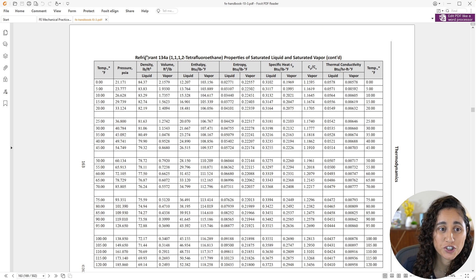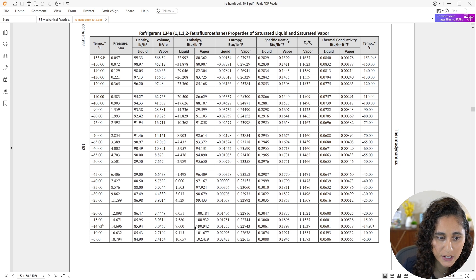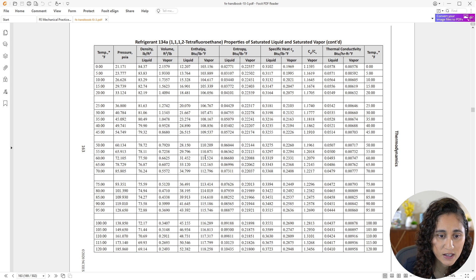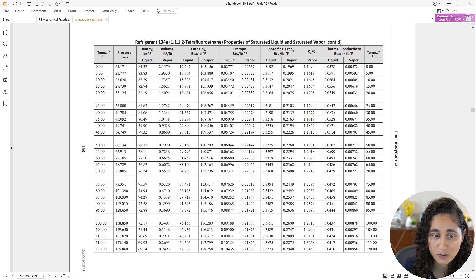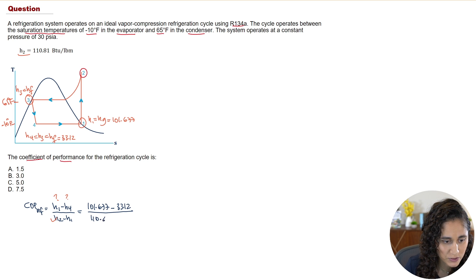Going to the reference manual for R-134A: at minus 10 degrees Fahrenheit, we look at the enthalpy columns for saturated vapor, and the value is 101.677. This is h1. Then at 65 degrees Fahrenheit, we look at the enthalpy for saturated liquid, and the value is 33.12. This is h4. Now plugging into the COP equation: h1 minus h4 over h2 minus h1, that is (101.677 − 33.12) divided by (110.81 − 101.677).